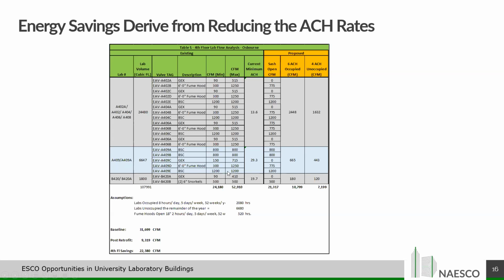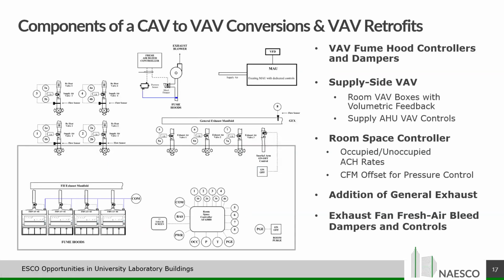Now, what we found was, we took this off the valve schedule and came up with this analysis, but then we used the BMS to trend the exhaust fans and the makeup air units that were serving the labs. And we found that the actual result was somewhere between these 2 numbers, which one would suspect. It was not varying much, but the number we settled on was around 36,000 CFM of exhaust from those labs. So this savings number actually grew. But it's all about reducing those air change per hour rates in the labs. That's where the energy savings comes from. Whether it's a constant air volume to VAV retrofit, or just a retrofit of an existing VAV system, you're always going to calculate those air change rate changes and derive your savings from that.